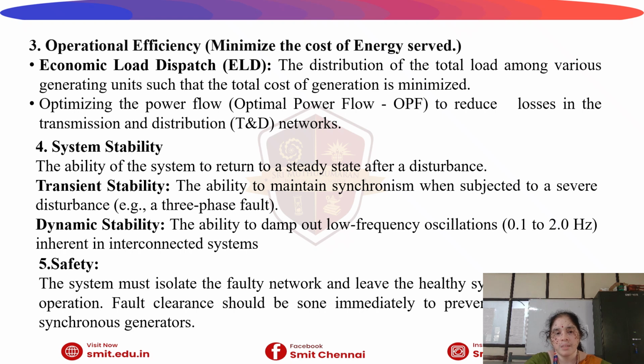System stability is the fourth important requirement. That is the ability of the system to return to the steady state after a disturbance. The main disturbance occurs due to transients. Transient stability is very important, and it is the ability to maintain synchronism when subjected to severe disturbances, for example, a three-phase fault. The dynamic stability of the system, the ability to damp out the low frequency oscillations, that is 0.1 to 2 Hz, inherent in the interconnected system, is very important.